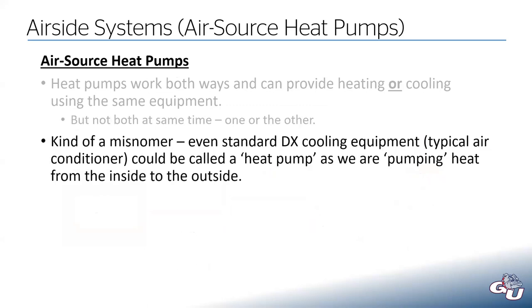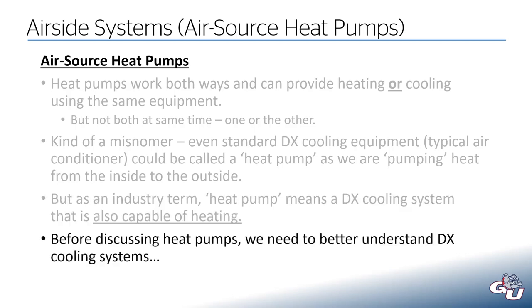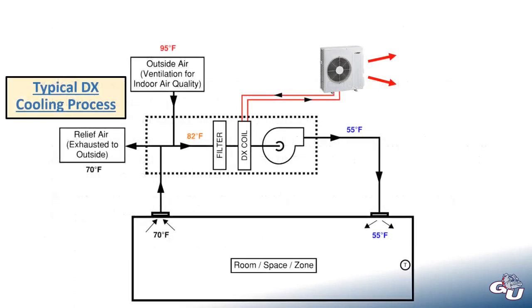This term 'heat pump' is kind of a misnomer. It's not really a correct term because even a basic air conditioner is still a heat pump in the sense that we're moving heat from one place to another. But when we're talking about heat pumps in the HVAC industry, heat pump specifically means a DX cooling system that is also capable of heating by running that cycle in reverse. So if somebody tells me this building has heat pumps, I take that to mean it can provide heating and cooling. Before we get into heat pumps, we first need to dive into a better understanding of how a basic DX cooling system works.